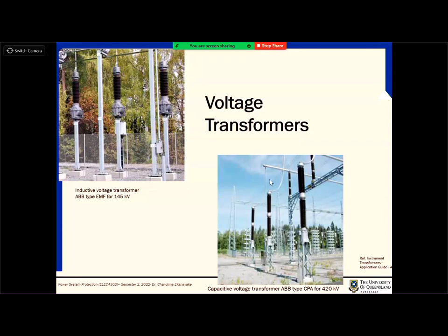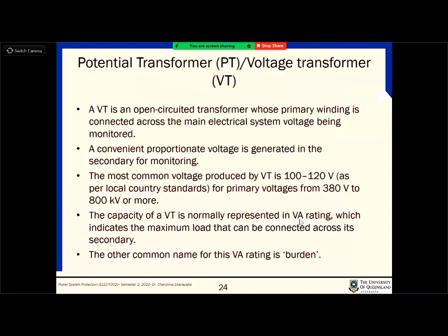So this also depends on the size. Say here it is a 420 kV substation. Therefore, you need much longer insulators. That's why it has 2 columns. So a VT is very similar to the normal power transformer, not like a CT, because it is just changing the voltage from one level to the other. Usually the secondary voltages are from 100 to 120 volts, because those are the typical voltages used by the relays, right? So 100 to 120 is very common.